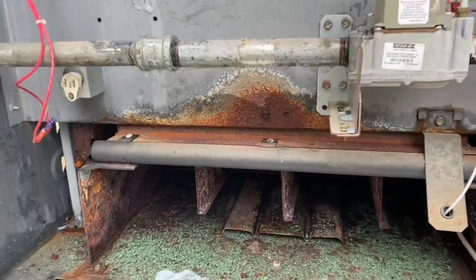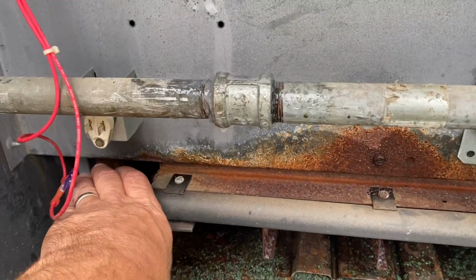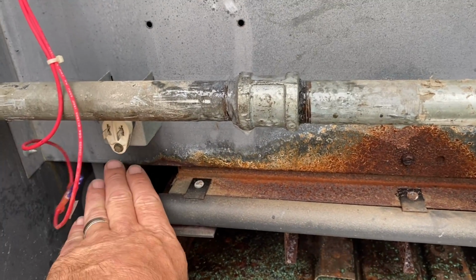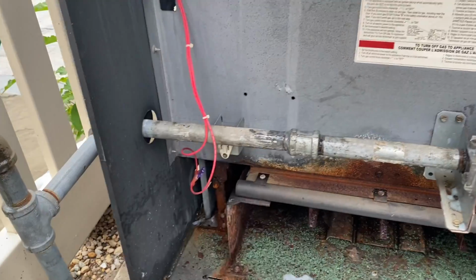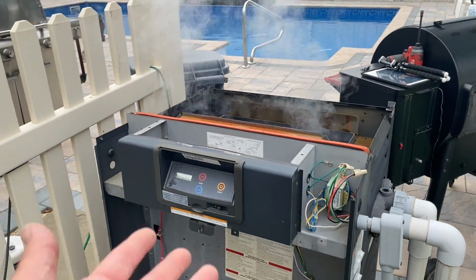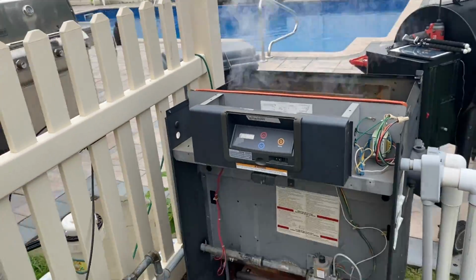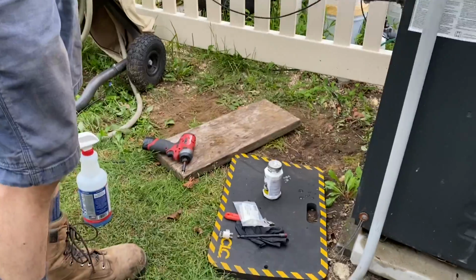And I do not have rollout present. There's my rollout switch, it'll be right there, and I can keep my hand there. We're good. Let's put a new rollout switch. We'll wait for this to die down, and again, I bought him some time, and as long as it's running safely, we're good. The transformer?